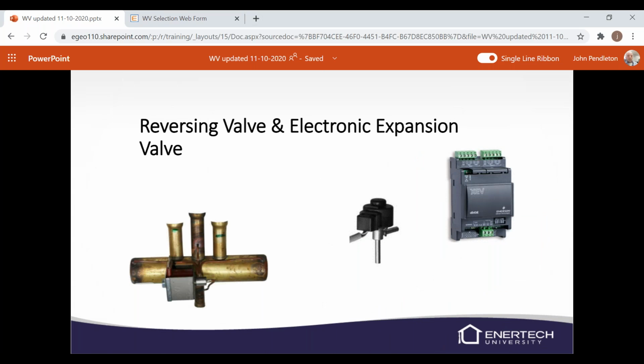We do have a reversing valve in the system. And in the middle of this screen is the electronic expansion valve. And then the box to the right of the expansion valve is what controls that expansion valve. It's got some lights on there that'll flash at you, and it'll say open, close, TX or something like that. So when it's working, those should be flashing at you.